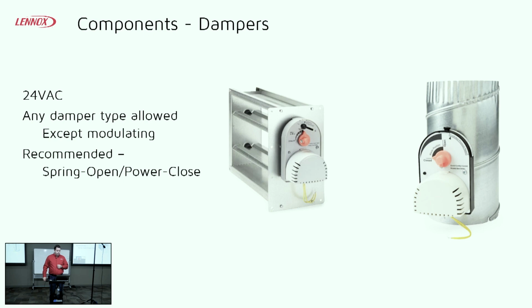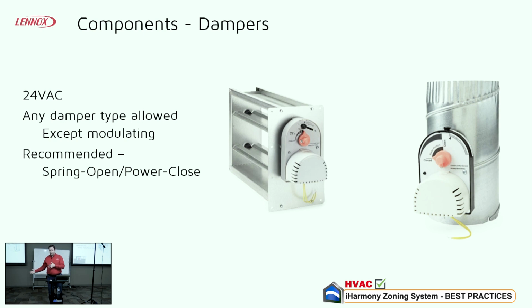So, 24-volt dampers. Basically, we can use any type of damper on here that's not modulating. The system's just going to give us a 24-volt, either open or closed signal. So it can be spring open, power closed, or it can be a power open. It can be a 3-wire that takes 24 volts to open it and 24 volts to close it back again. All those will work, but it just doesn't provide the modulating signal on a system like that.